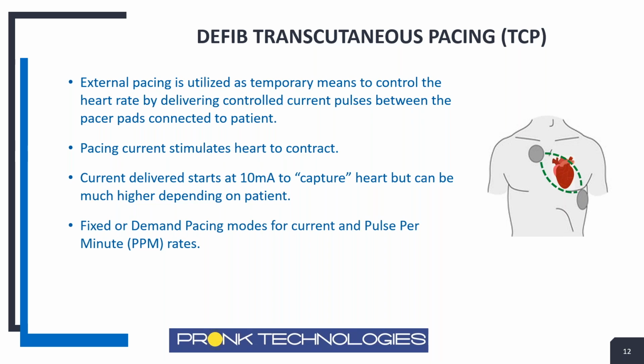You have demand pacing, or you have fixed pacing. Fixed pacing basically is, okay, I'm going to apply a certain amount of current, and I've set it on the defibrillator, and it's going to output it. It's going to output a certain pulses per minute, and it's going to capture the heart at X pulses per minute. And so that's fixed mode, which is the most commonly used mode for preventive maintenance.